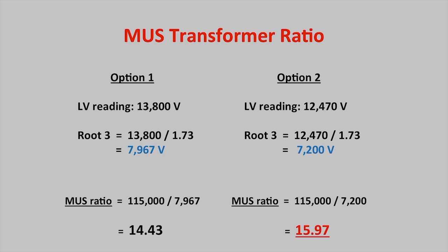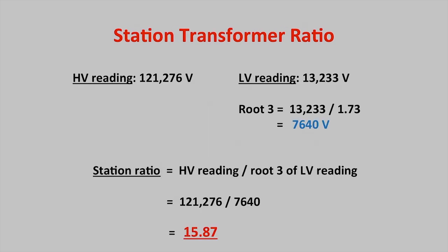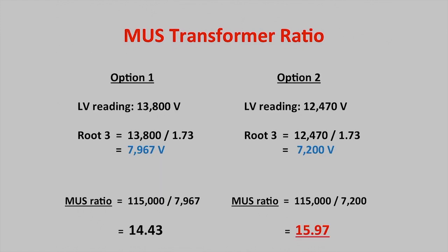115,000 divided by 7,200 equals 15.97. Since the station transformer ratio is 15.87, the 12,470 volt option is the best setting to ensure the greatest range of operation on the ULTC.